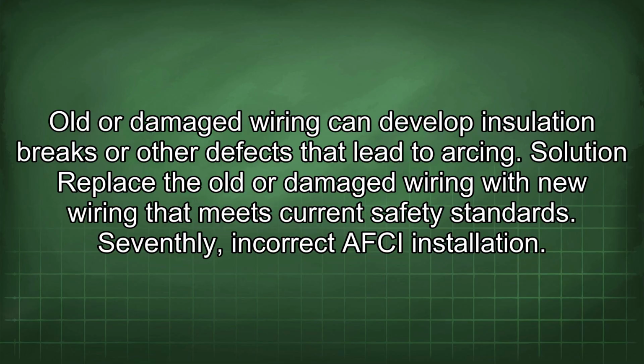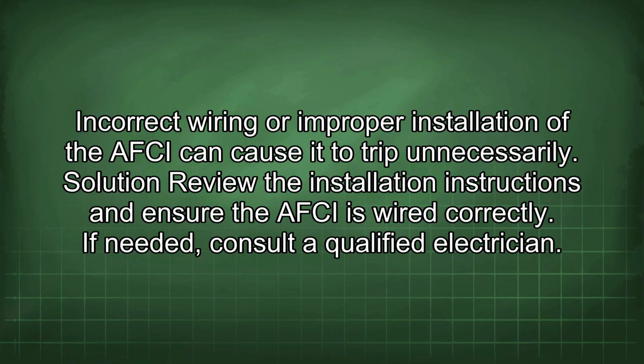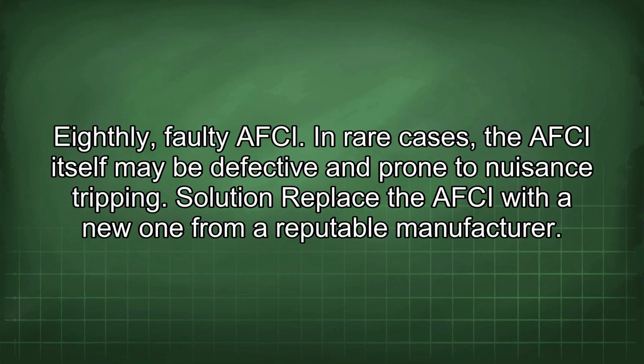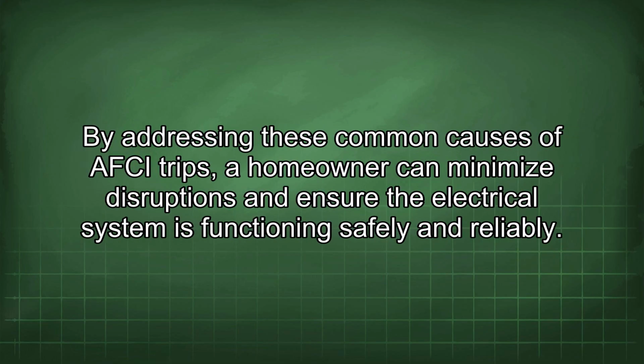Seventhly, incorrect AFCI installation. Incorrect wiring or improper installation of the AFCI can cause it to trip unnecessarily. Solution: review the installation instructions and ensure the AFCI is wired correctly. If needed, consult a qualified electrician. Eighthly, faulty AFCI. In rare cases, the AFCI itself may be defective and prone to nuisance tripping. Solution: replace the AFCI with a new one from a reputable manufacturer. By addressing these common causes of AFCI trips, a homeowner can minimize disruptions and ensure the electrical system is functioning safely and reliably.